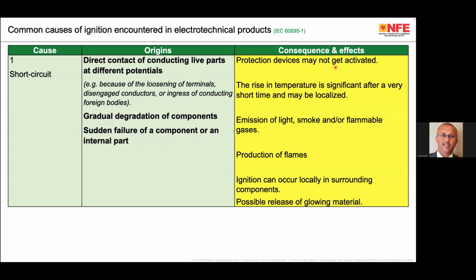Protection device may not get activated. The first one means the protective device, such as a fuse or MCB, is not working properly. It is not tripping in time, which is the first cause. The rise in temperature is significant after a very short time and may be localized. Emission of light, production of flames, ignition of surrounding components, and the release of glowing material. These are the consequences of short circuit.